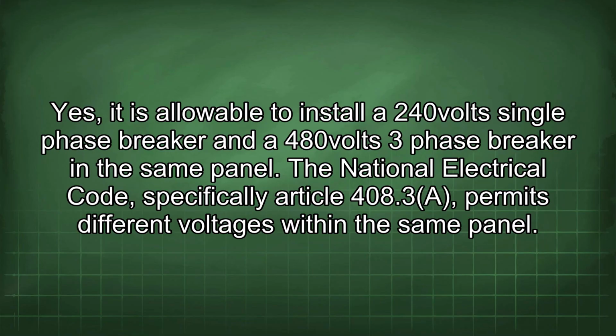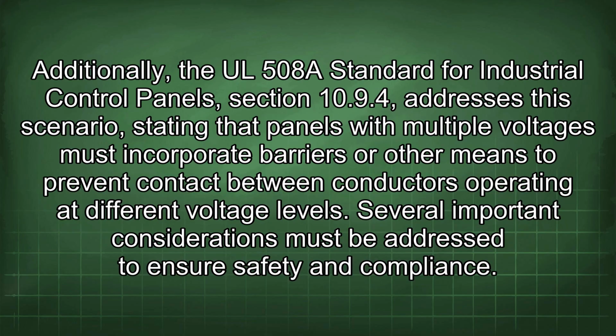Yes, it is allowable to install a 240 volts single-phase breaker and a 480 volts three-phase breaker in the same panel. The National Electrical Code, specifically Article 408.3a, permits different voltages within the same panel. Additionally, the UL 508A standard for industrial control panels, section 10.9.4, addresses the scenario, stating that panels with multiple voltages must incorporate barriers or other means to prevent contact between conductors operating at different voltage levels.